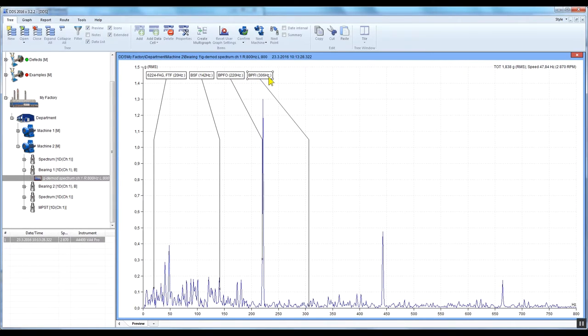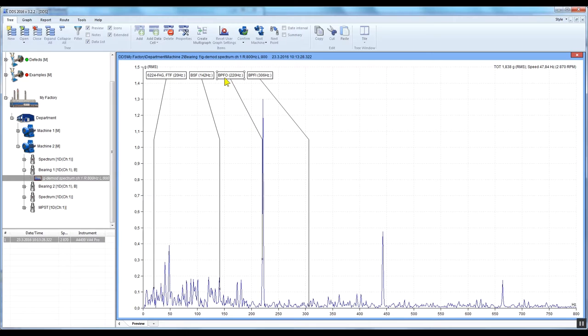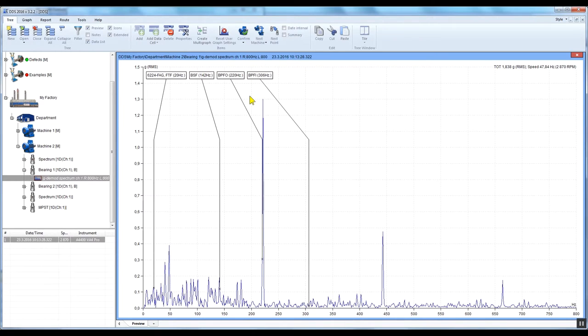In our example, we can see that there is a significant energy spike on the BPFO, which represents a bearing outer race defect. Bear in mind that to display bearing fault frequencies, you need to know the speed of the machine.